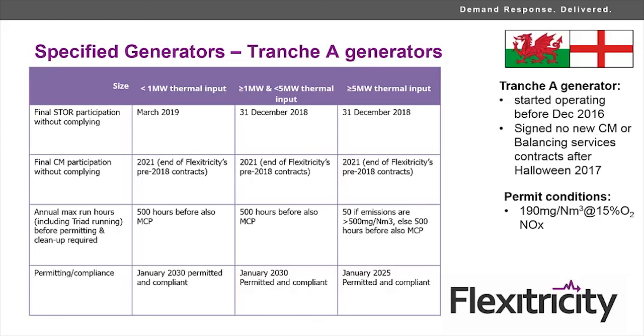On the other hand, if it's bigger than that, then it must do fewer than 50 hours a year if its emissions are greater than 500 milligrams per normal cubic meter. An unabated standby diesel generator has higher emissions than that; unless you're a magician, you're going to be breaching that limit. And in terms of compliance, anything smaller than 5 megawatt thermal input has until January 2030 to be permitted and compliant with the permit, and the larger ones January 2025.